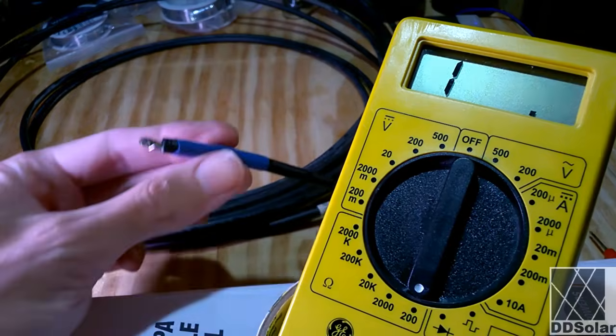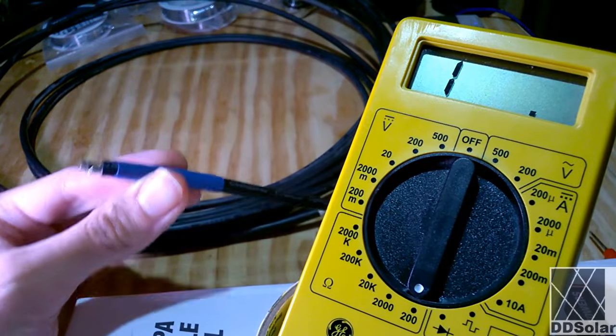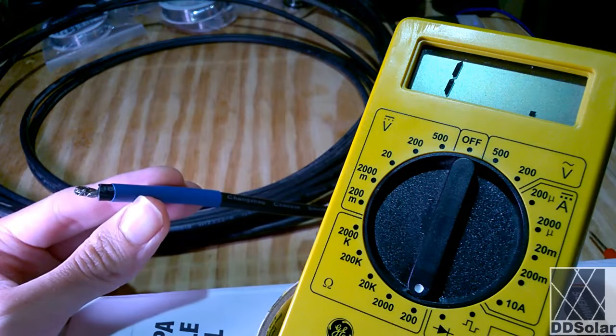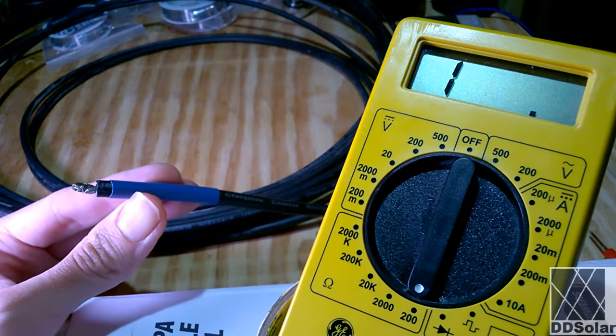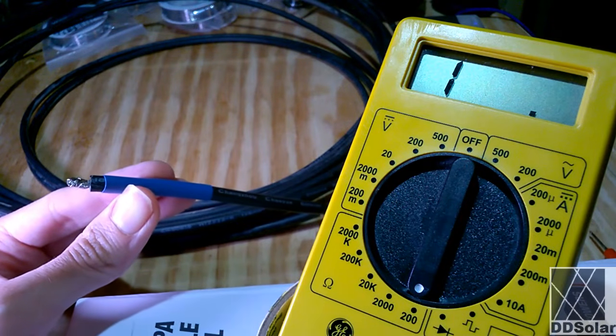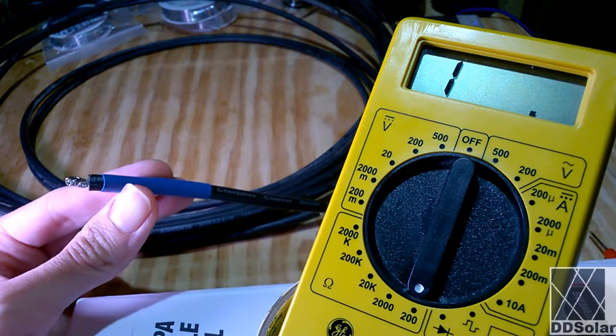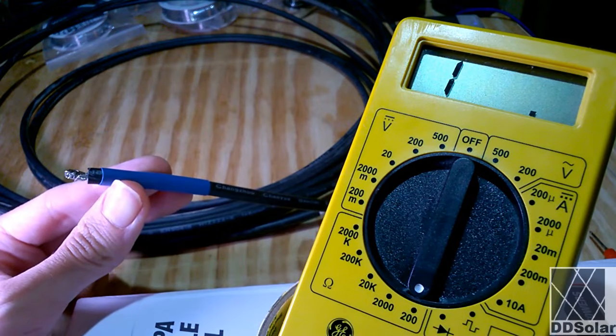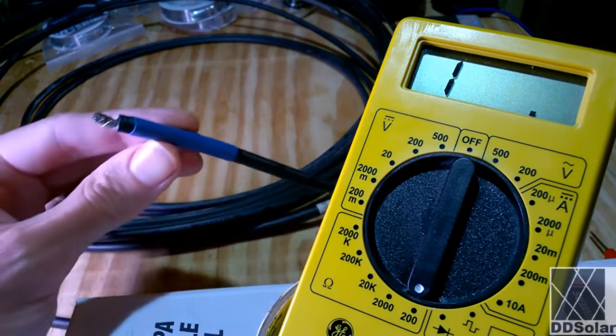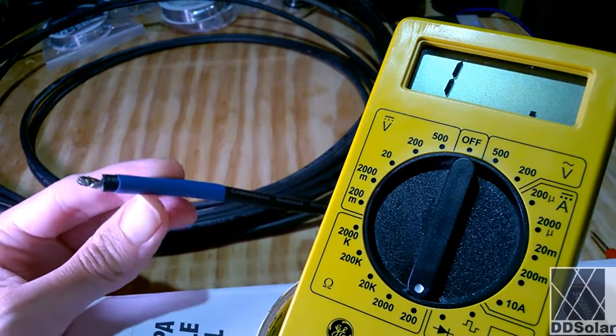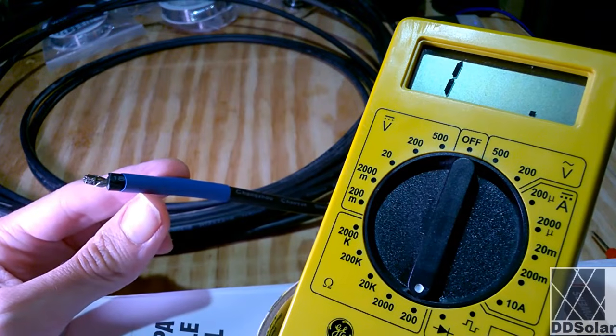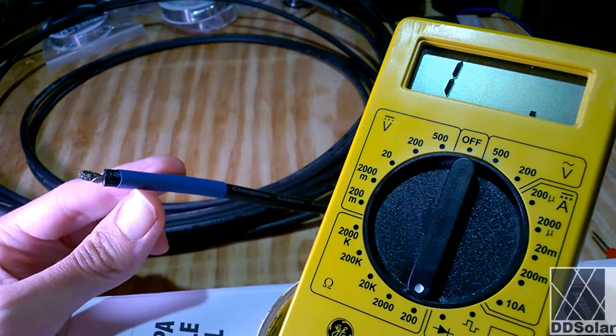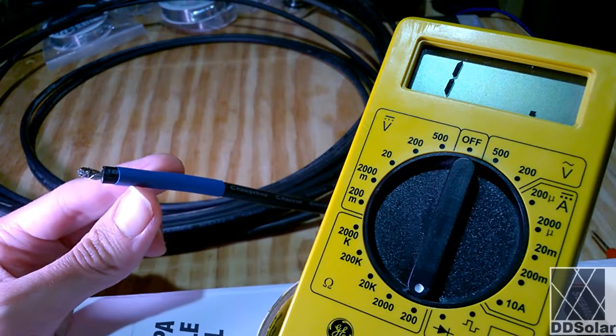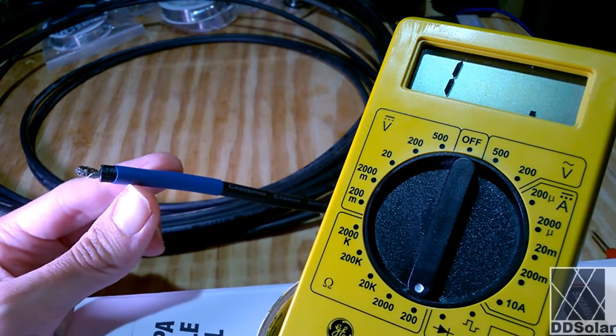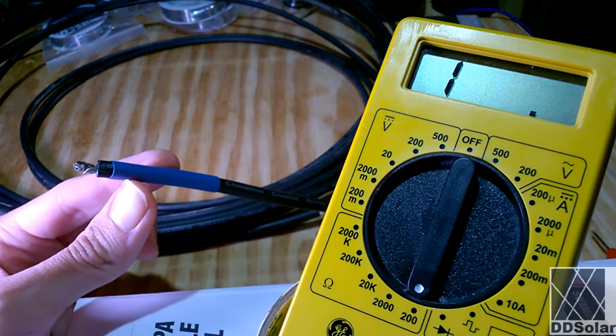You can use it to identify which cable is which. And by switching it to voltage, you can even find which one is putting out power. If, for example, I had an array of solar panels and I had 20 or 30 wires coming through, I could disconnect the solar panels and use the ohms setting or the continuity check setting on the meter, if it has one, to determine which of these wires goes where and then mark them with a color tag at either end. And by process of elimination, I could identify every single wire, without actually seeing where they go underground or through the conduit or through the walls or wherever they're going.